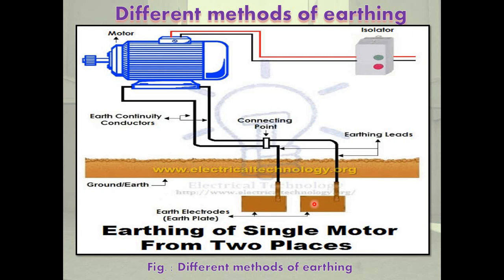The repair and maintenance work of high voltage apparatus should not be undertaken unless the apparatus is made dead, isolators are open and locked, and earthing switches are closed and locked. HV conductors should be discharged and connected securely to earth. Place caution notices and danger notices near the workplace and near the switching terminals. Use a safety belt, gloves, and hat. Do not use wet clothes, wet shoes and metal tabs. Boards like "Don't switch on, man at work, danger 440, don't touch" and likewise.